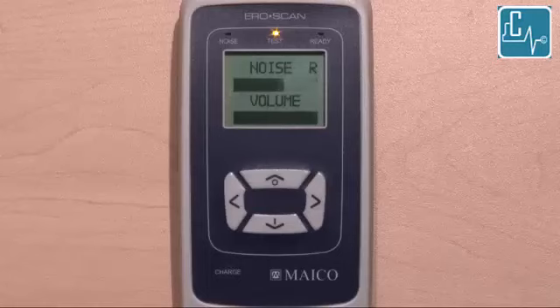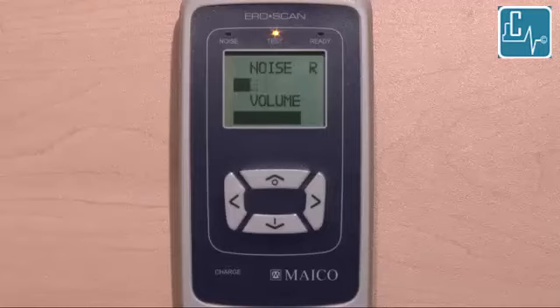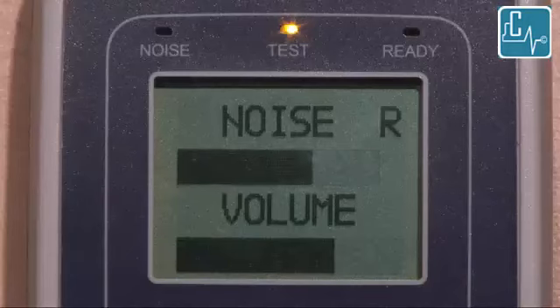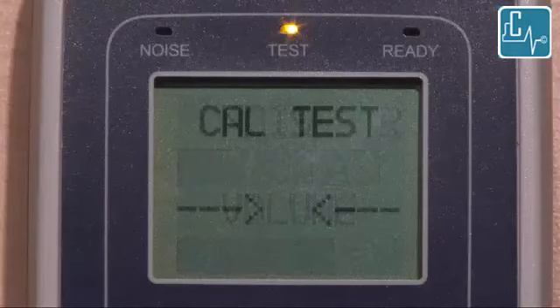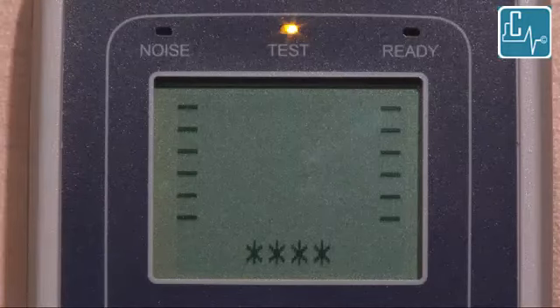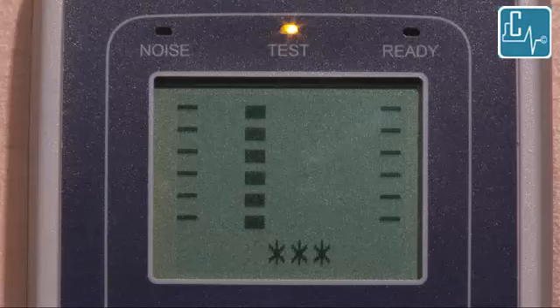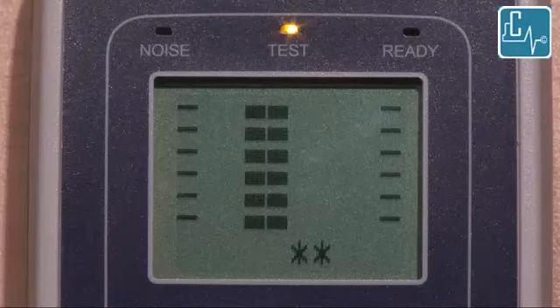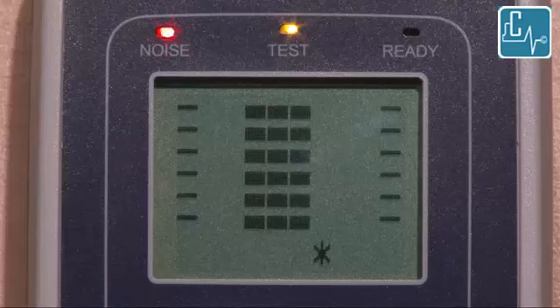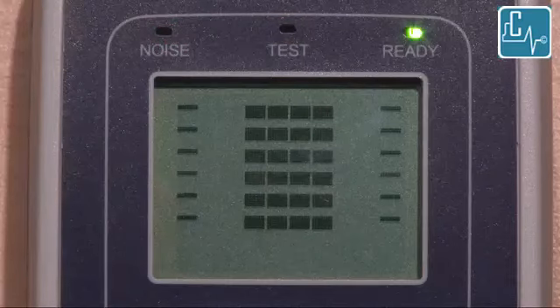If the noise or volume bars do not decrease, try to reposition the probe, use a different ear tip size, or eliminate noise sources within the test environment. Once the bars have reached sufficient levels, the ERO SCAN will conduct a calibration test in the ear and then automatically move on to the OAE test. A signal-to-noise ratio graph will be displayed. This graph shows the level of the OAE measured above the noise level at each of the test frequencies.